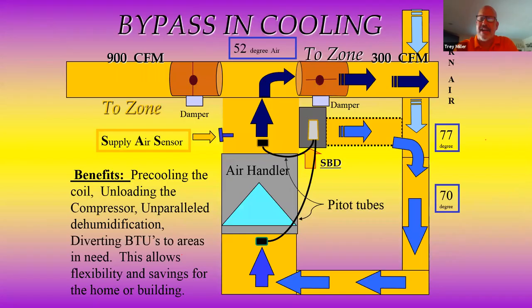Well, how you hook up the bypass, you're going to have pitot tubes. The pitot tubes, here's one in the supply, one in the return. We want them to be somewhere between 1 and 2 feet from the plenum itself, from the unit itself, to make sure we're getting a good static pressure reading across the system. Because guys, this is what's going to set up the entire system. Now, let's just say that we put our pitot tubes in a place and we're reading a different static. That's not necessarily the end of the world, because whatever it captures in whatever position it's in, that's what it's going to go back to. So that's going to maintain that static that it captured, which, as long as we don't have air noise in our home and everything, we should be okay.